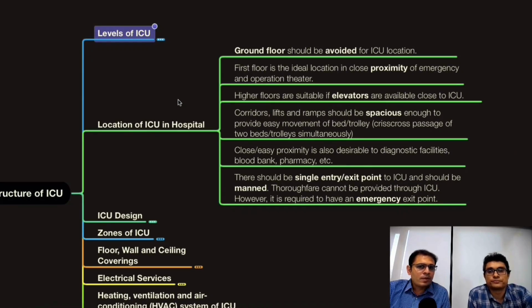It should be proximal to the diagnostic facility, blood bank and pharmacy, and there should be a single entry and exit point of the ICU. It should always be manned because unnecessary people should not get entry into the ICU. Thoroughfare cannot be provided in any ICU, and it is always required that you have an emergency exit.